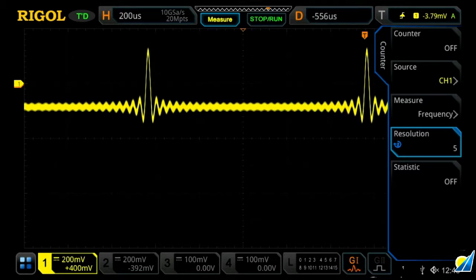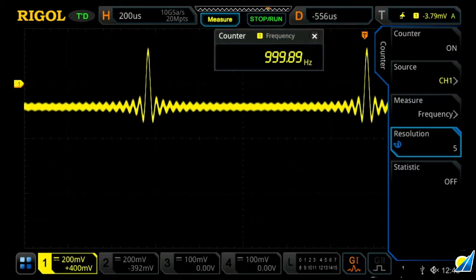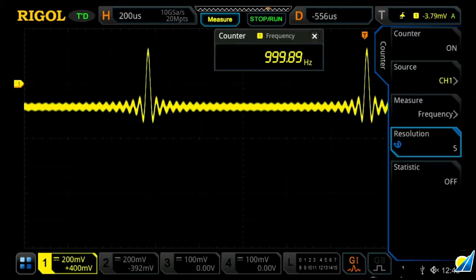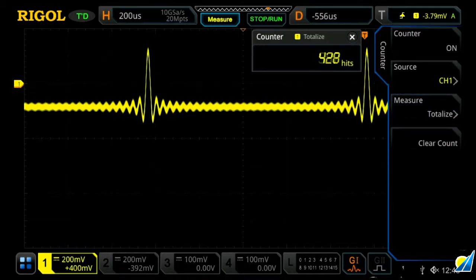And once you've turned it on, we'll see it's displaying the frequency of channel one, and we can change this to be one of our other channels. We can also change our measurement type to be either frequency, the period, count up, or the totalizer, which is really just counting up the total number of trigger events that have occurred.